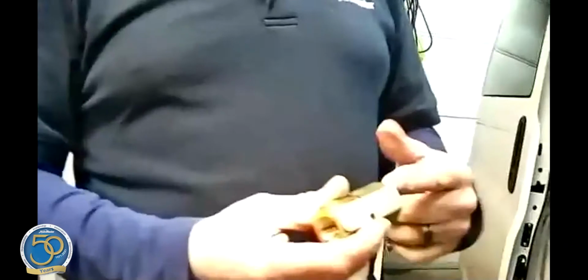So anyway, the check ball is going into a seat, and that seat gives us the ability to create back pressure. There's a spring on top of the seat, and then there's this other half of the body, and they screw together, and the solution is going to flow through this. And what it does is it creates a back pressure on the outcoming water, a drop of 100 psi, which gives us the ability to inject the chemical stream into the front of this check valve, and that gives us the draw that we're looking for to go to the tool.